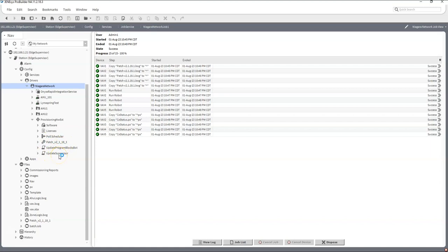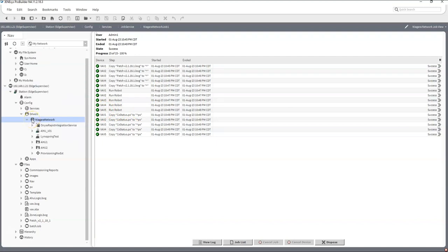You won't have to do anything with the patch itself. The supervisor update again should work. However, I believe because I've mixed and matched controllers here, it can't actually go through each of them alone. So I think that's why the process failed there. But it normally would not fail, especially if you just have all the VAVs. However, we see that we have a complete success of the patch files. And again, if you need a complete list of the issues that it fixed or scenarios that it fixed, you can go ahead and read the release notes from the resource website.